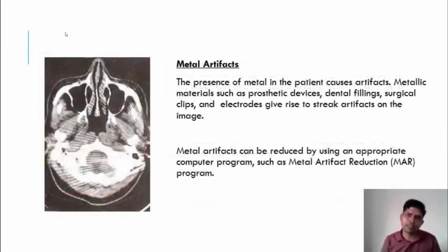Next is metal artifacts. When a patient, especially a female patient, comes for a CT brain and you forget to ask her to remove an earring, you can see this image that I kept in the slide. Due to that, a streak-like artifact is created by the metal. So you can ask the patient to remove metallic parts from the required area, or nowadays we have metal artifact reduction software available.